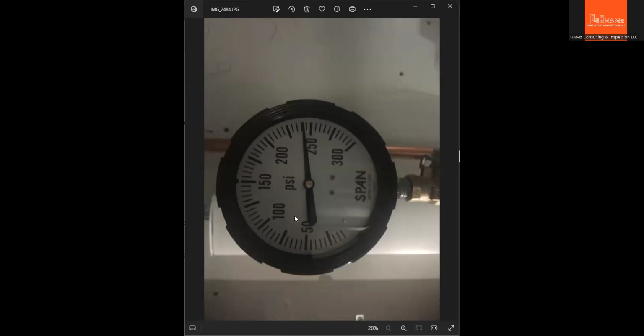So as much as possible, if you're witnessing a test, some building departments usually go on the job site before they pressurize the system, so that they can see this dial at 0 for accuracy. After the test they need to drain it out, and that dial arm should go back to 0 again. That means it was reading the correct pressure that will be used for the system. So that's part of the procedure that we usually witness and verify.